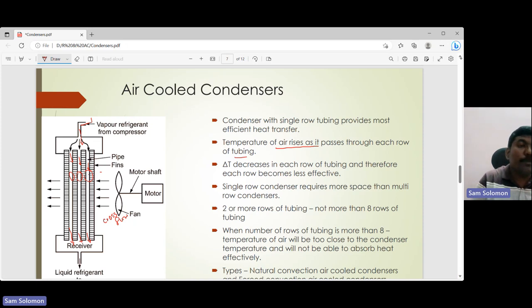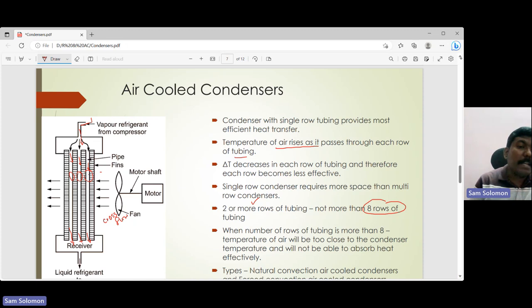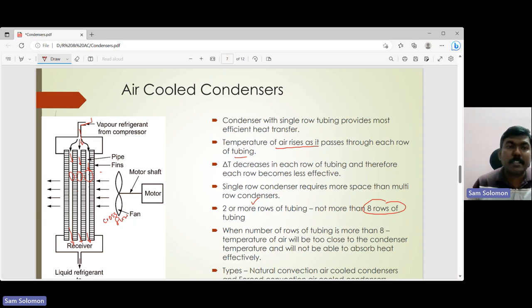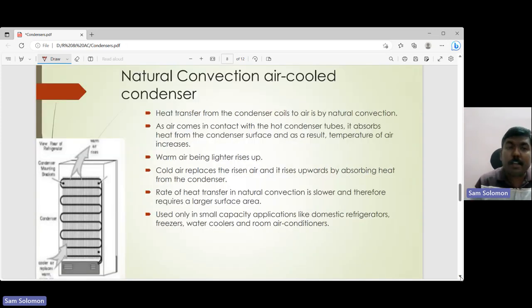A single long tube would increase condenser size, so multiple rows of tubing are used. However, there is a practical limit: you can have two or more rows but not more than eight rows. With too many rows, by the eighth tube, the air temperature and the refrigerant temperature may become nearly equal, making heat removal inefficient. So the efficiency of the condenser decreases when there are too many rows of tubing.